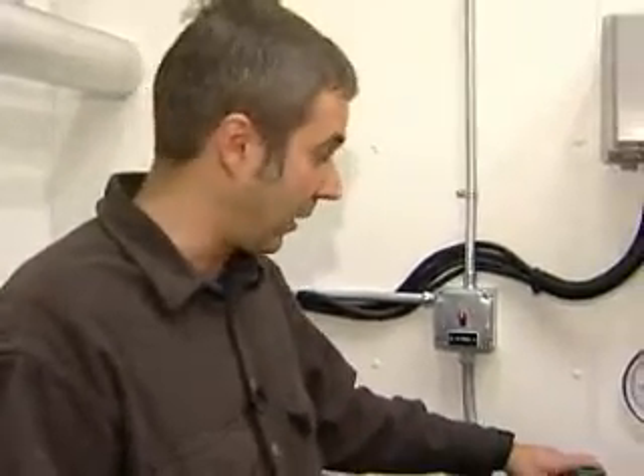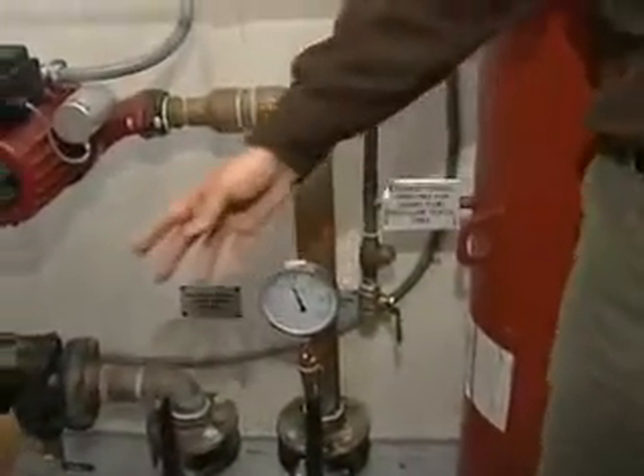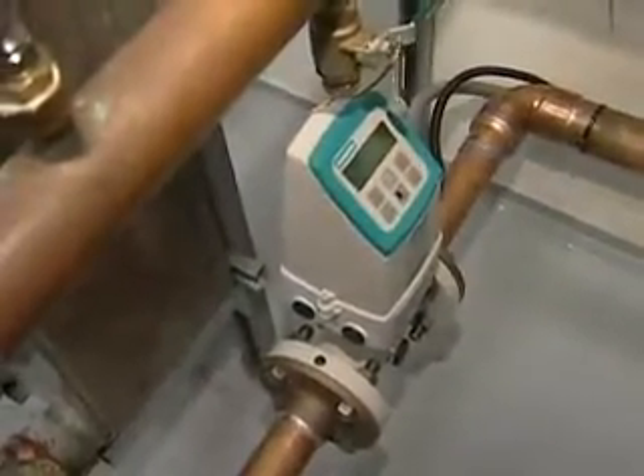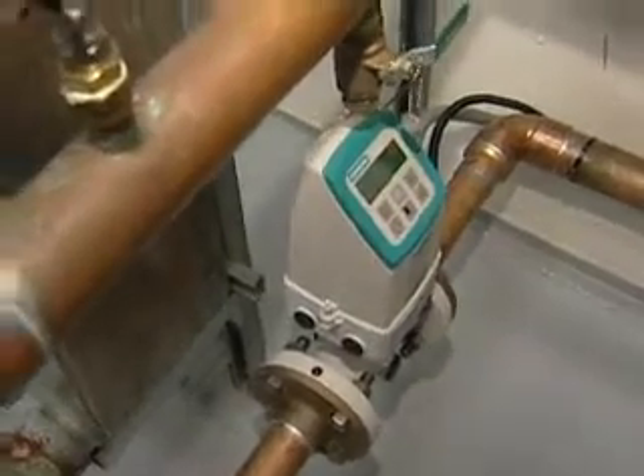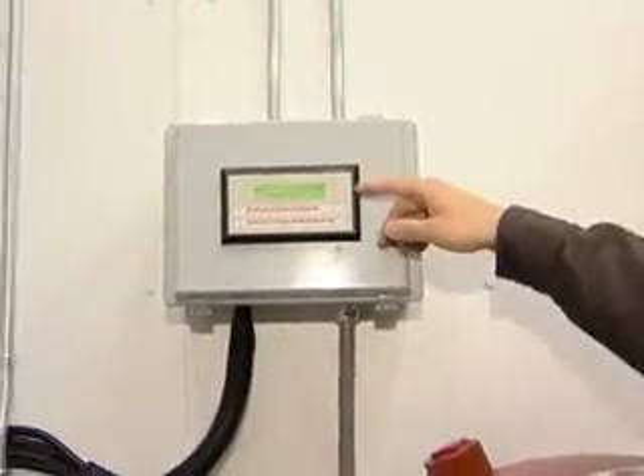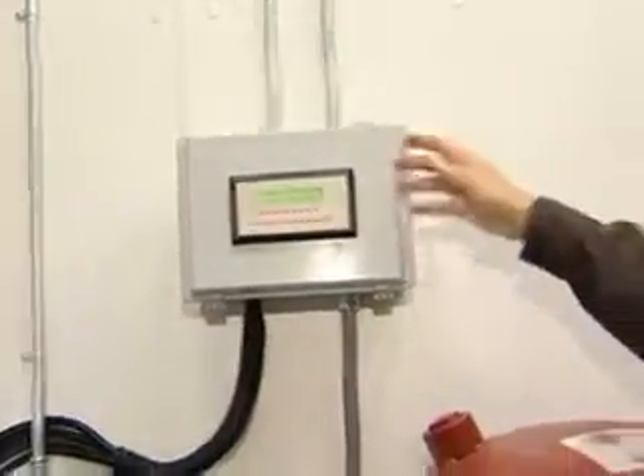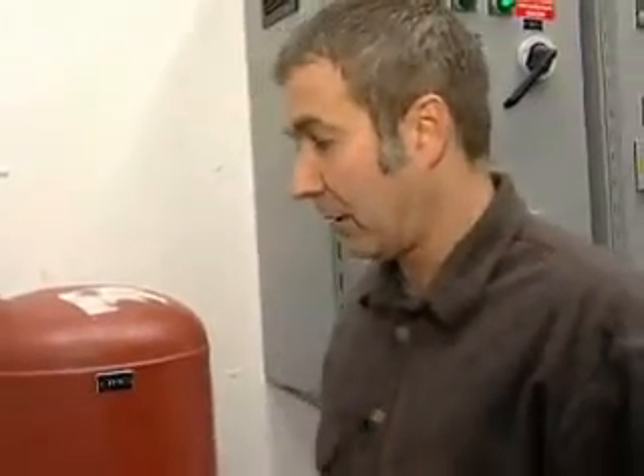Again, you have to make sure when you need to add fluid to the system that you use the exact same fluid that was installed, the same mixture, and again, you don't want to add local water to the system because you can clog up the heat exchanger. Okay, this system also has an energy meter. There's a flow meter down here in the piping. And up on the wall here, we have a flow computer. And so what this device does is measures the amount of energy that's being sent out. So it records the flow rate and the temperatures and the energy sent. So you can use this if you're charging for waste heat. You can use this as your billing method.